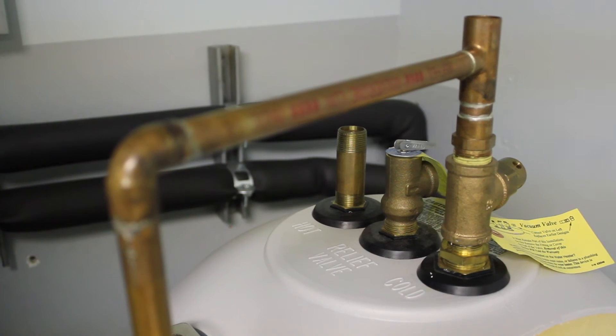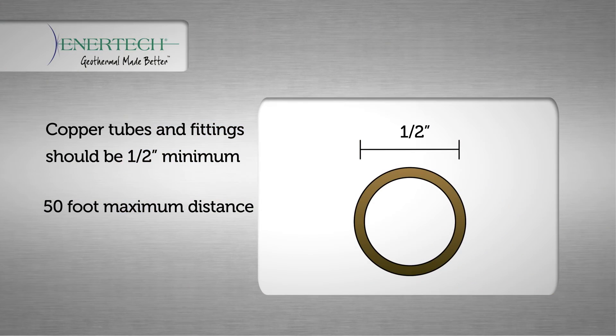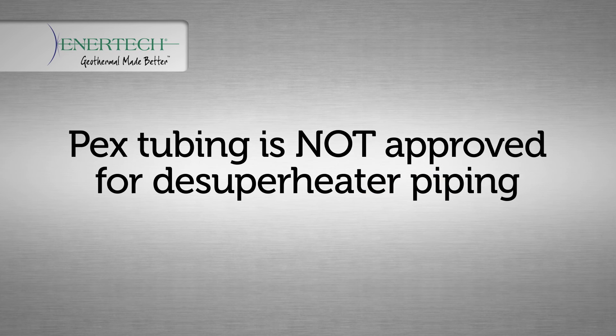All copper tubes and fittings for the desuperheater circuit should be half inch nominal size minimum with a maximum of 50 foot distance one direction. Piping should be insulated with 3/8 inch wall closed cell insulation. PEX tubing is not allowed for use in the desuperheater circuit.